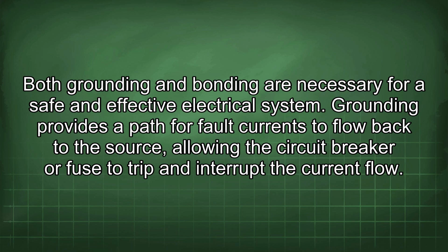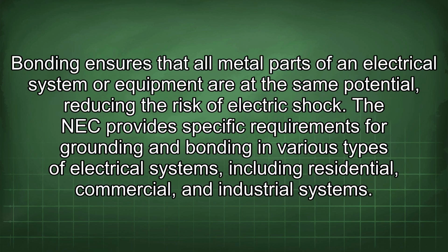Grounding provides a path for fault currents to flow back to the source, allowing the circuit breaker or fuse to trip and interrupt the current flow. Bonding ensures that all metal parts of an electrical system or equipment are at the same potential, reducing the risk of electric shock.